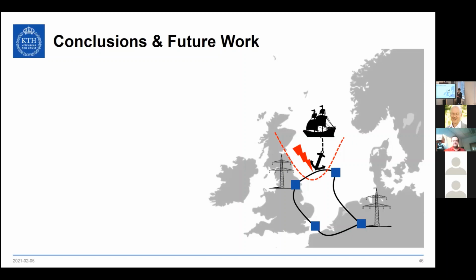The higher fault resistance will result in a bit of a dampened signal, such that the signal might not be so strong that you want to detect. So the margin is a design parameter that I want the system to fulfill, and for that I have to take into account the fault resistance as well. For example, I take the worst case such that I get a dampened fault detection signal, and then I design the system such that the margins are fulfilled for that case. But the fault resistance does not have an immediate impact on the margin—that's a fixed parameter that I input into the design.